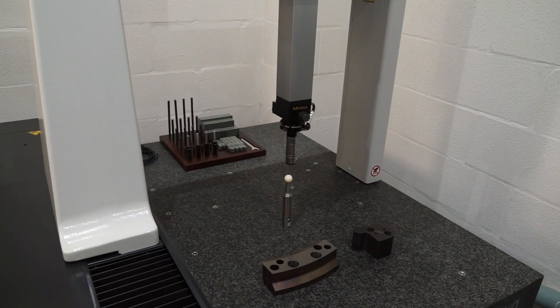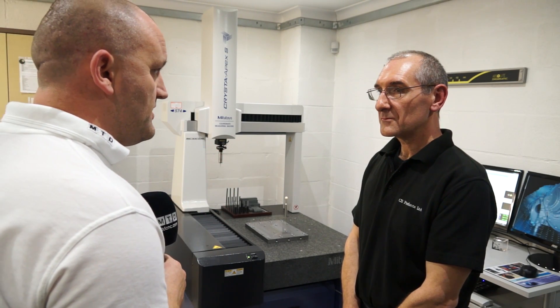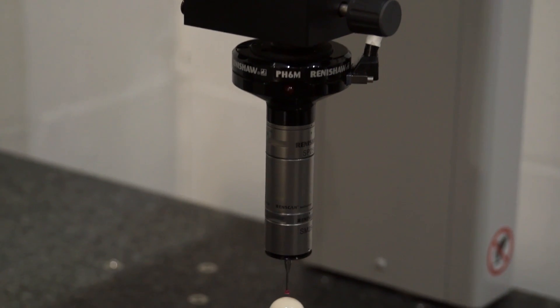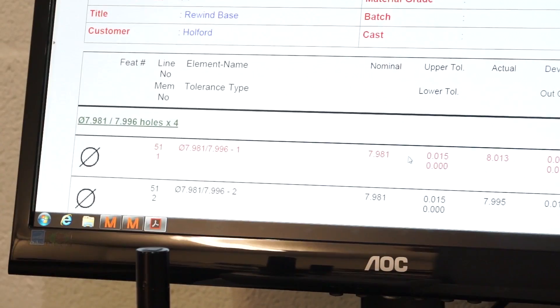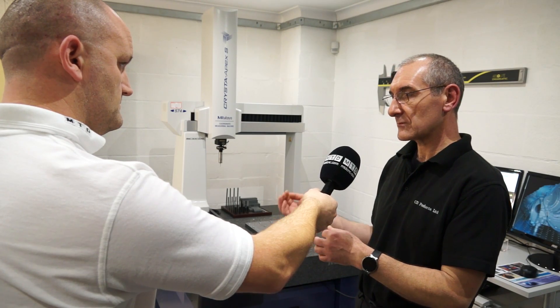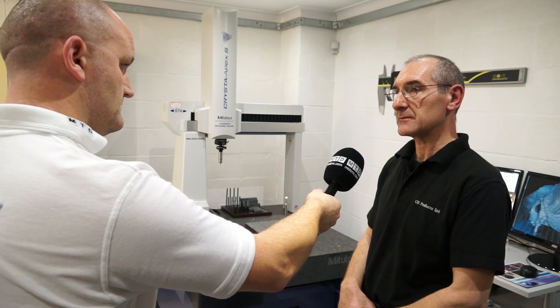How do we know the part is correct? I know the screen might say the part's correct, but how easy is it to calibrate the machine? The calibration is done on the calibration ball — you can either write a program so it will automatically calibrate, or you can manually take the probe over to the calibration ball and it will automatically calibrate.